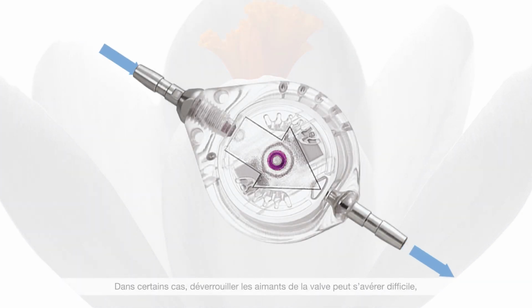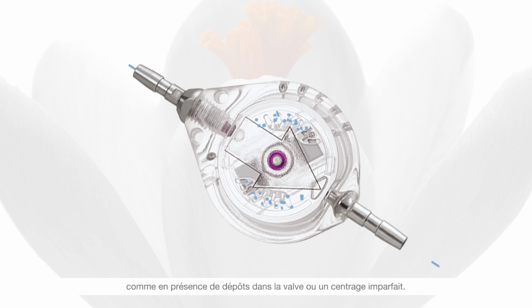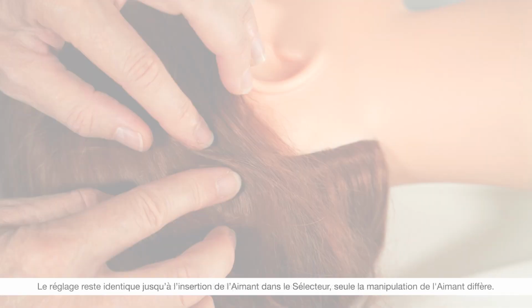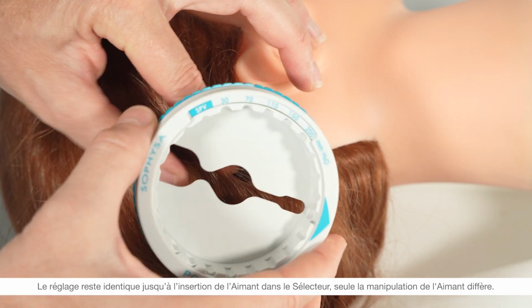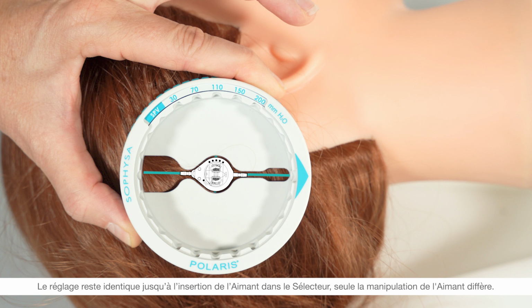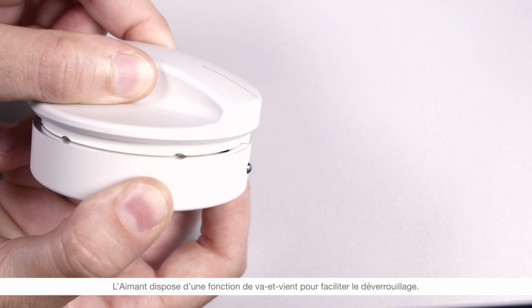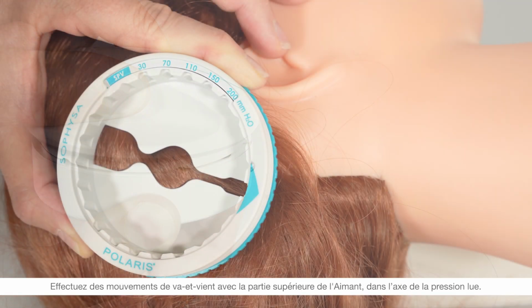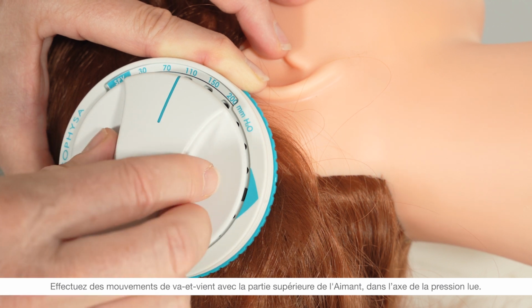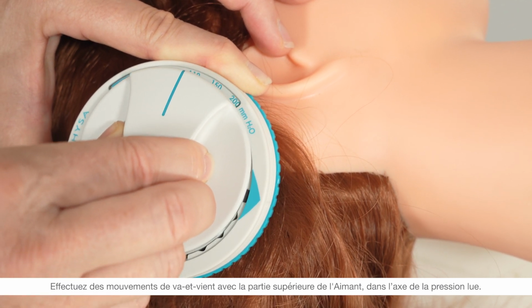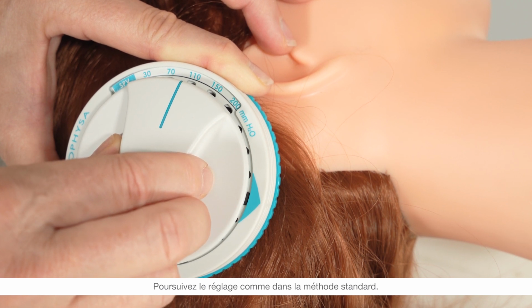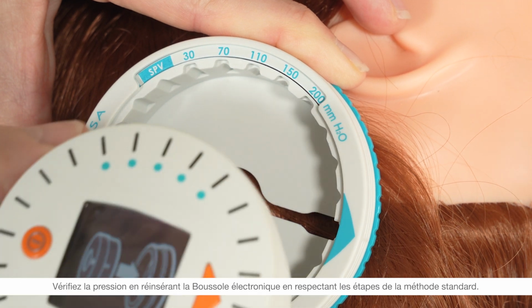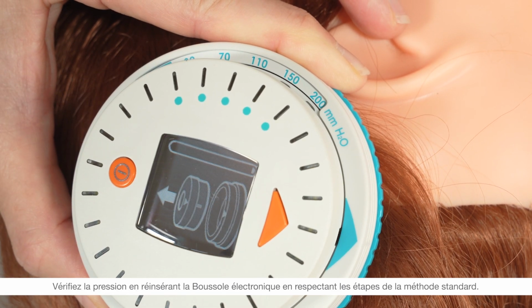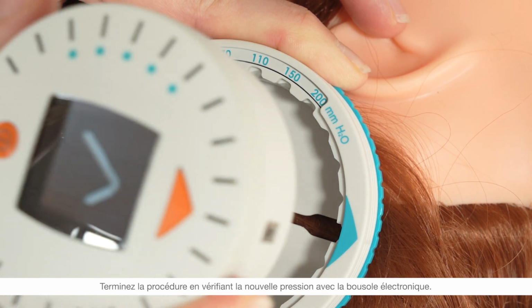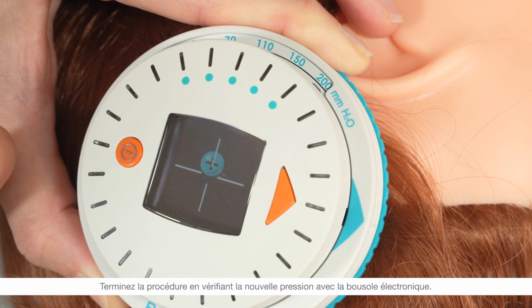Unlocking the rotor's micromagnets within the Polaris valve may be difficult if the CSF is especially viscous or contains debris, or if locating the center of the valve is imprecise. The adjustment steps are mostly identical to the standard method. Only the magnet manipulation differs. In these situations, performing multiple backwards and forwards movement of the magnet inside the locator along the axis of the implanted valve rotor can facilitate the unlocking of these micromagnets. Then recenter the magnet handle and follow the steps of the standard adjustment method, always finishing by confirming the new pressure setting with the compass.